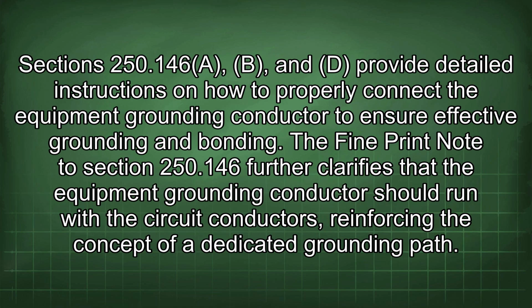Sections 250.146(A), (B), and (D) provide detailed instructions on how to properly connect the equipment grounding conductor to ensure effective grounding and bonding. The fine print note to Section 250.146 further clarifies that the equipment grounding conductor should run with the circuit conductors, reinforcing the concept of a dedicated grounding path.